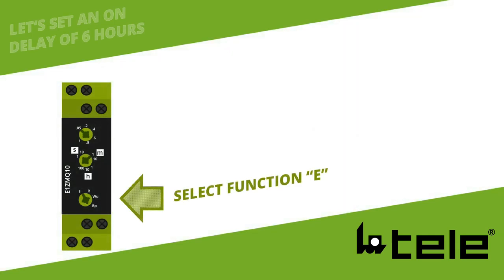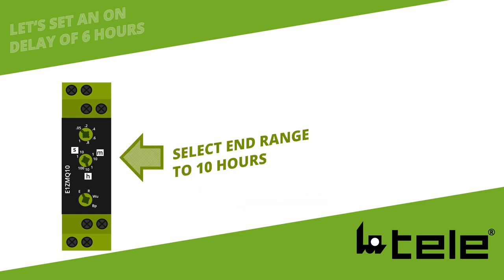The first step would be to select the function E, which stands for on delay. The second step would then be to think: what kind of time range do I need? The time range is determined by the dial in the middle and allows you to select your end range. You will also have the chance to change that during your operation, but in our circumstance, since we want a 6-hour time delay, we need to select something larger than 6 hours on the dial. Hence, we're selecting the 10-hour range in the middle dial.